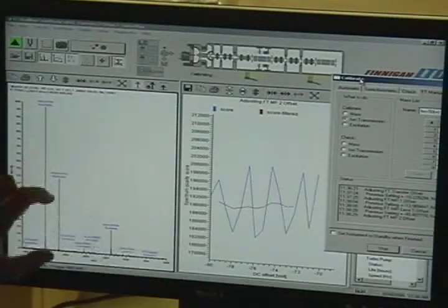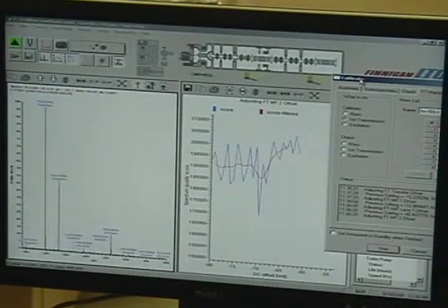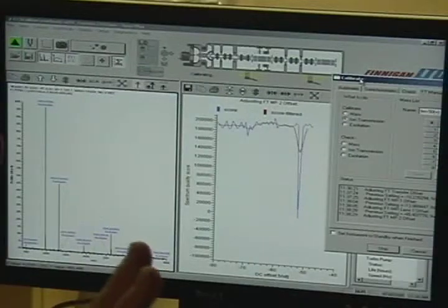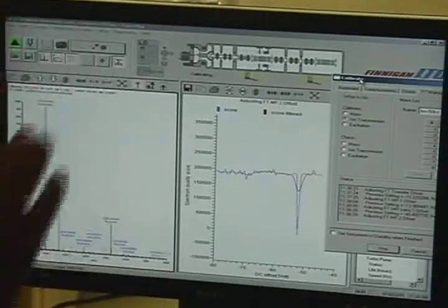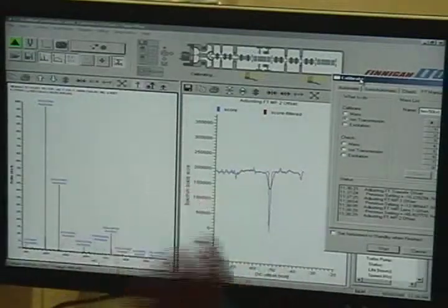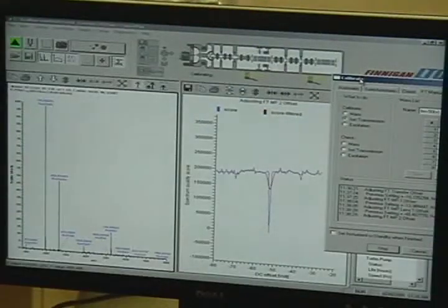Then add in one or two compounds. Pick some antibiotics at 350, 400. That way when it calculates the spectrum quality, the score will be calculated with a heavier bias towards the low masses, and that will shift your transmission calibration to low mass. See how it works?